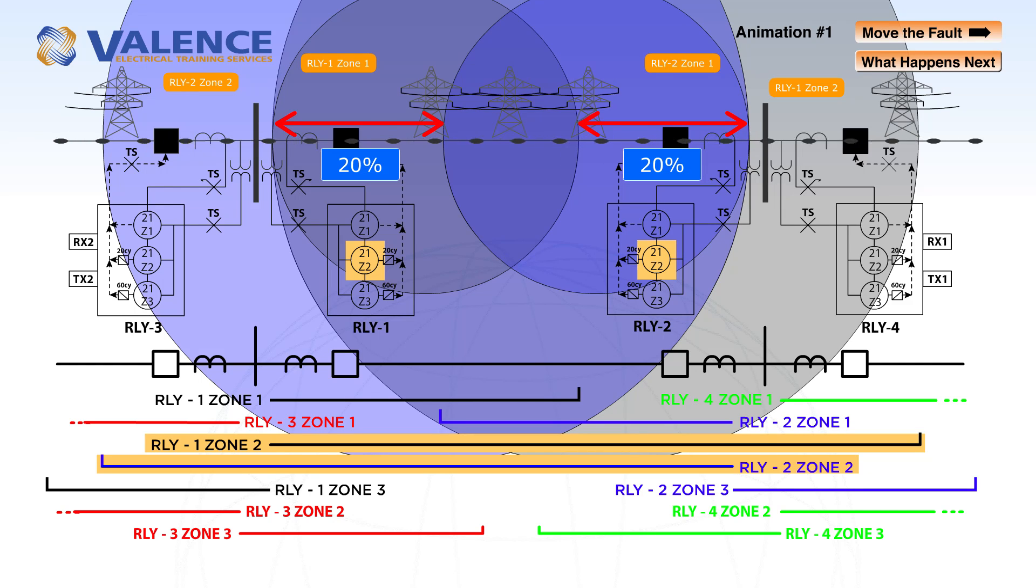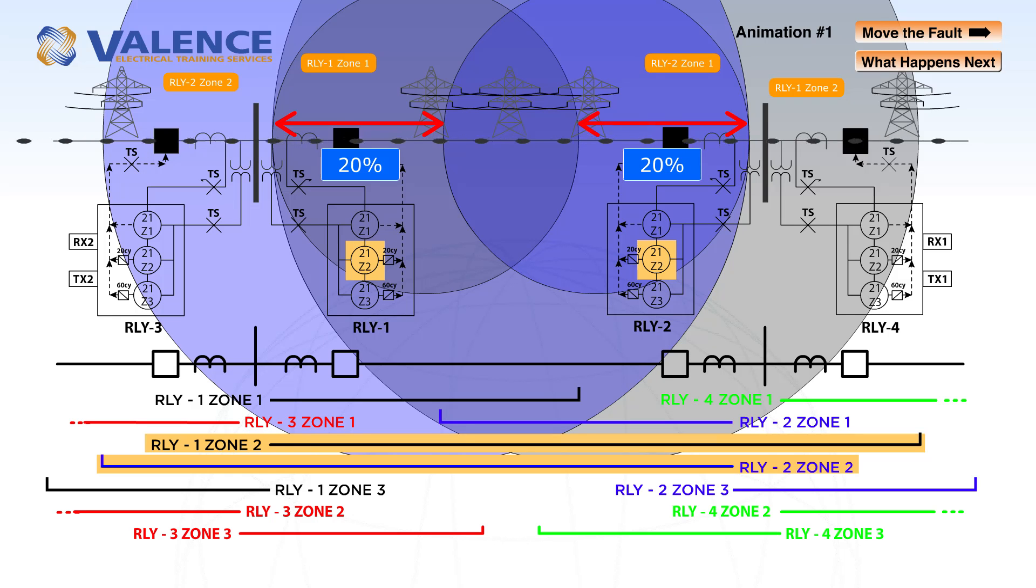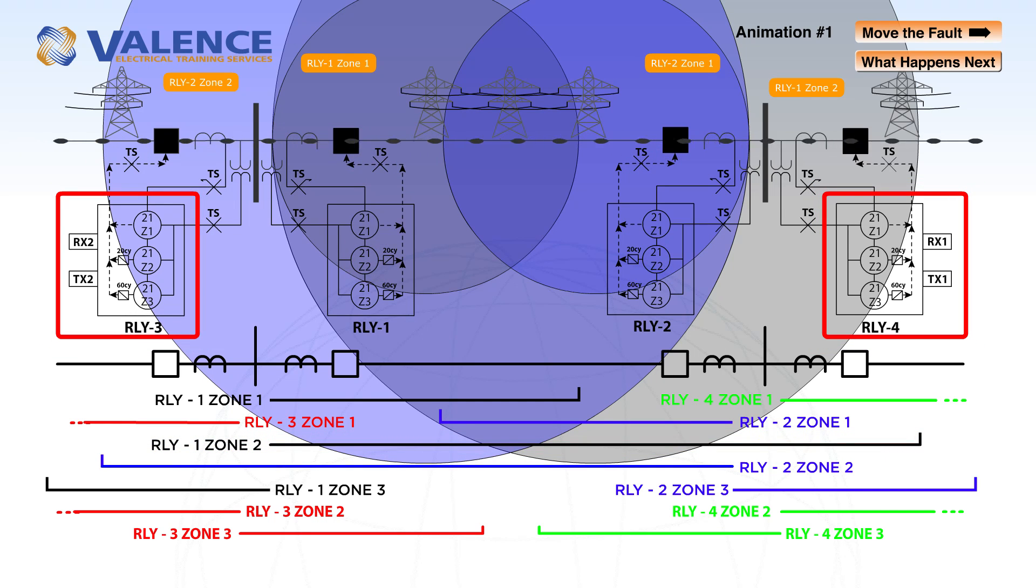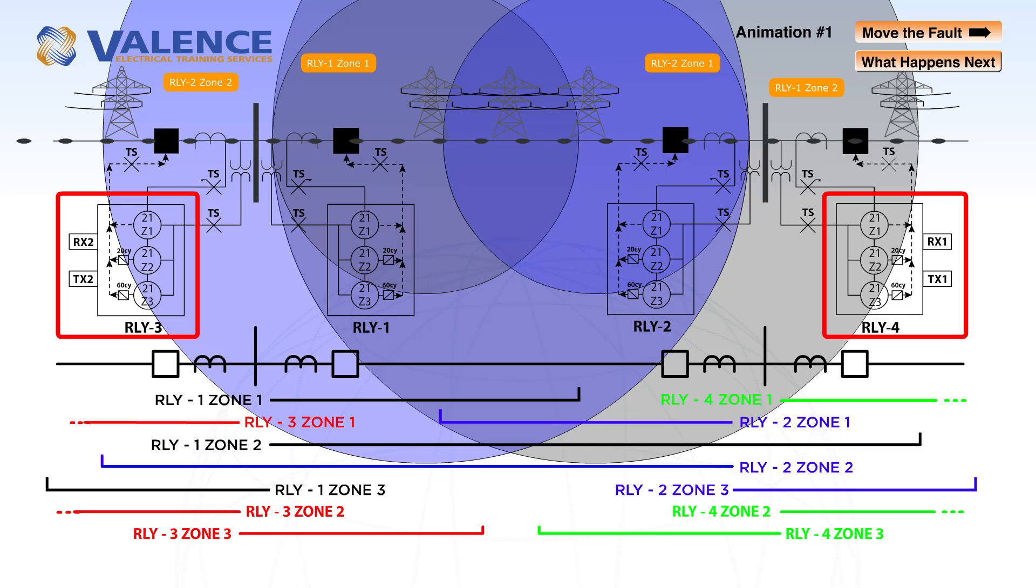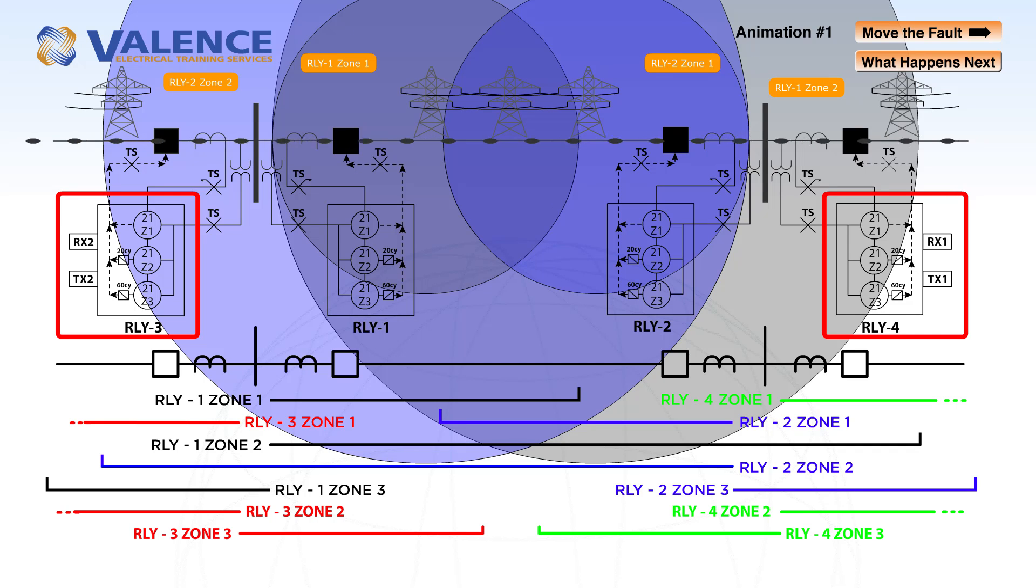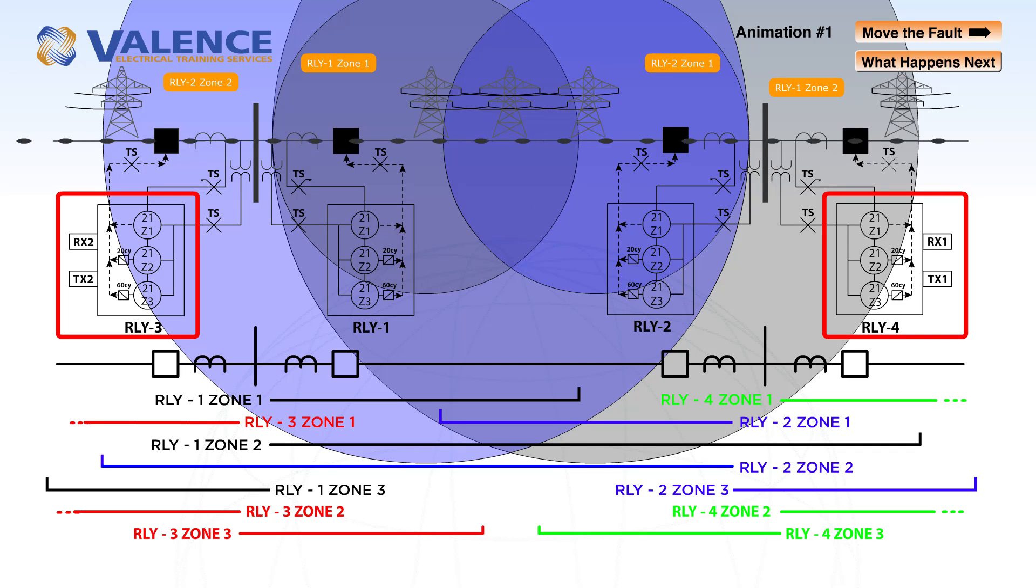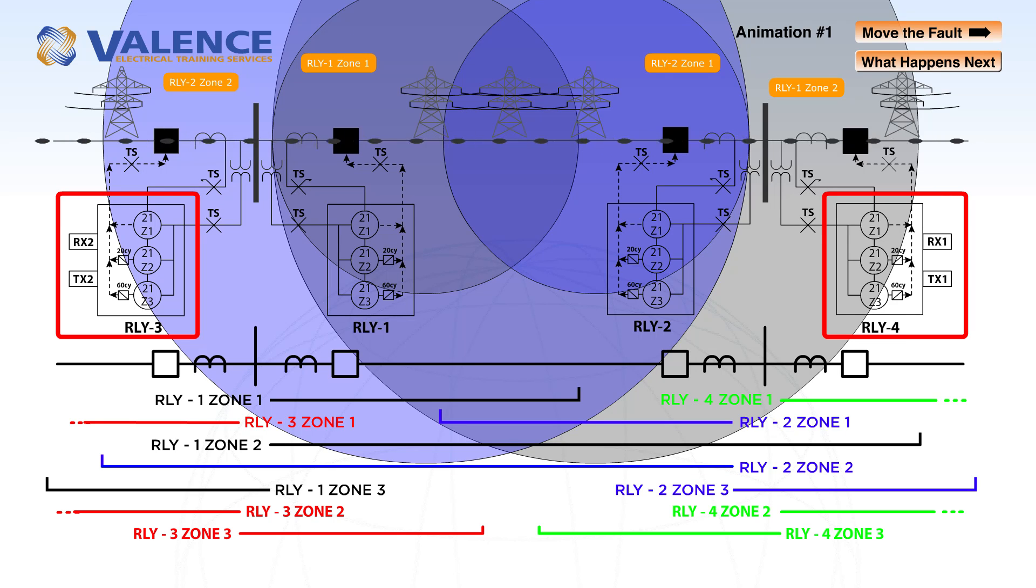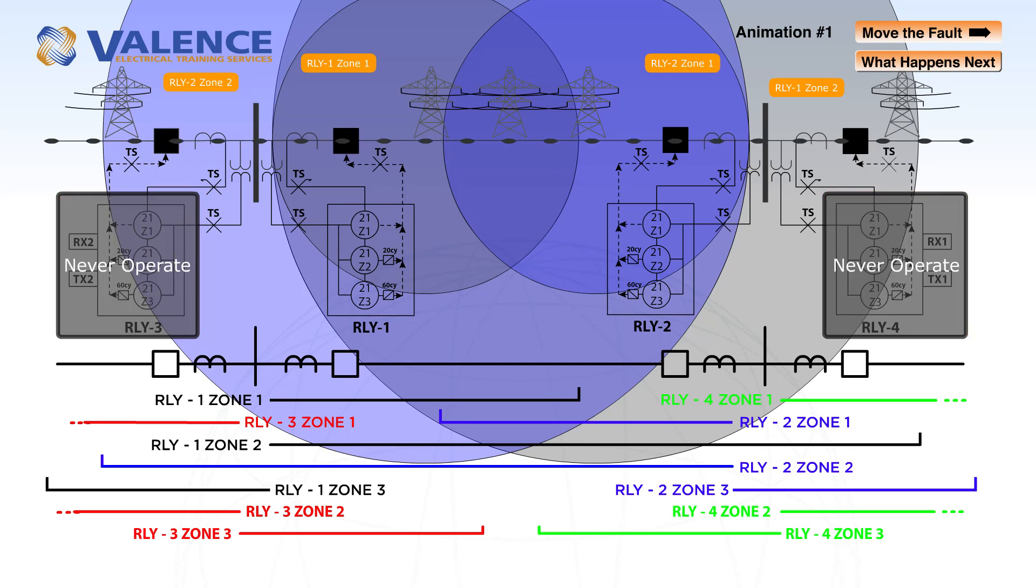Zone 2 also gives us the added benefit of backup protection for relay 4 and relay 3. For the purposes of this video, we will pretend that someone forgot to turn the battery charger back on after the station batteries in relays 3 and 4 were tested, so relays 3 and 4 will never operate.